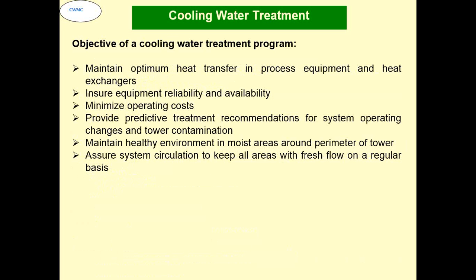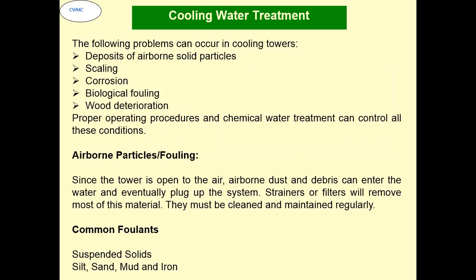The objectives of a cooling water treatment program are to maintain optimum heat transfer in process equipment and heat exchangers, ensure equipment reliability and availability, minimize operating costs, provide predictive treatment recommendations for system operating changes and tower contamination, maintain a healthy environment in moist areas around the perimeter of the tower, and assure system circulation to keep all areas with fresh flow on a regular basis. Generally, the following problems are observed in a cooling tower: deposits of airborne solid particles, scaling, corrosion, biological fouling, wood deterioration, etc. Proper operation of the procedure and chemical treatment can help us control all these conditions.